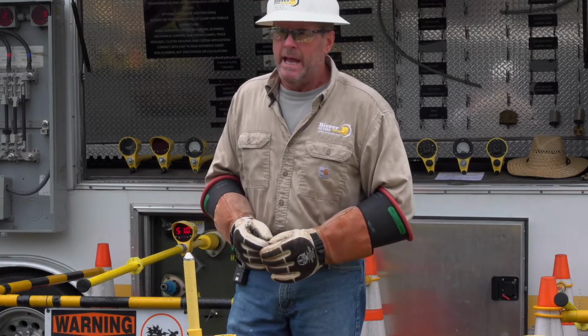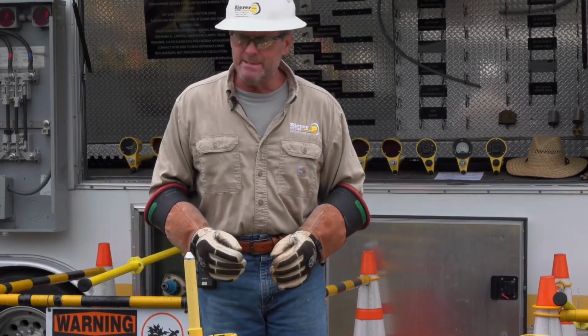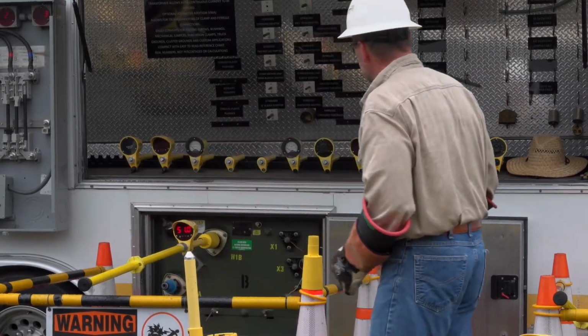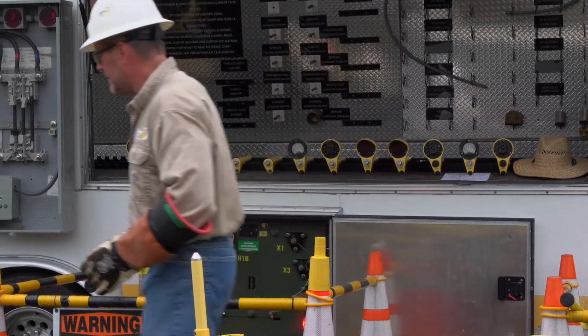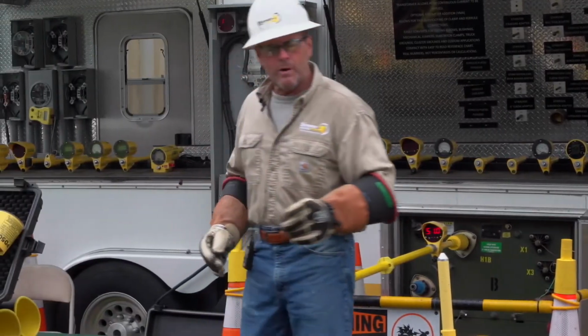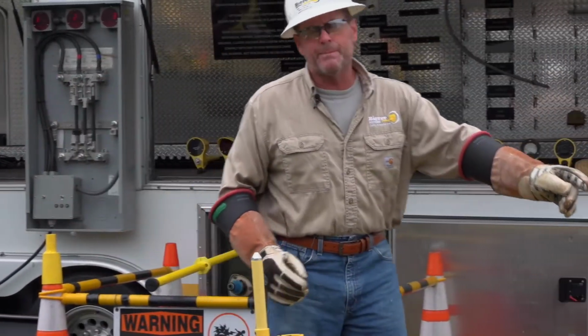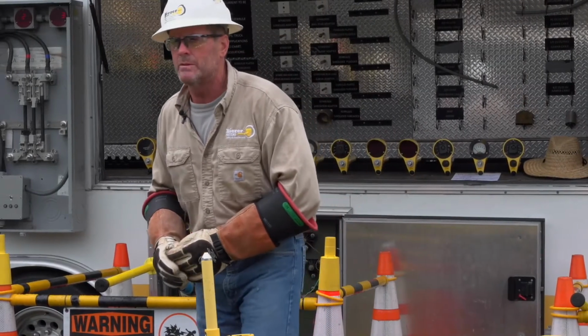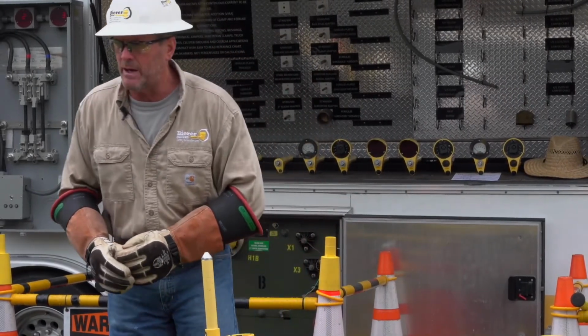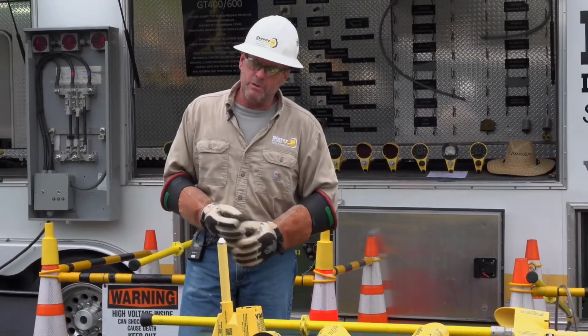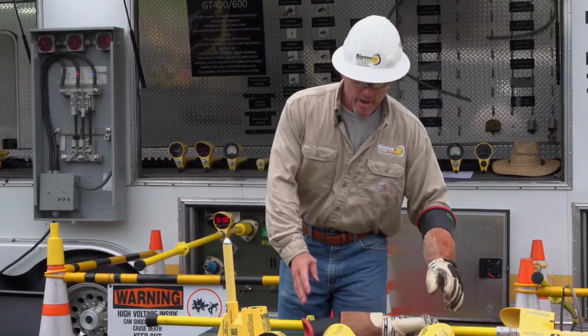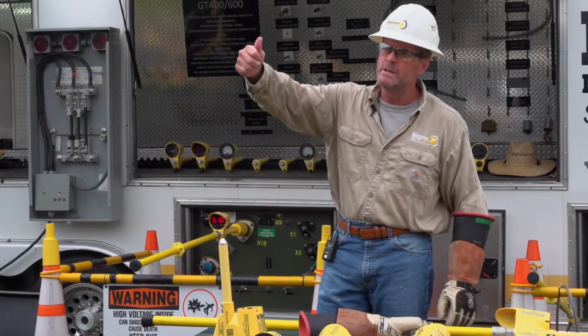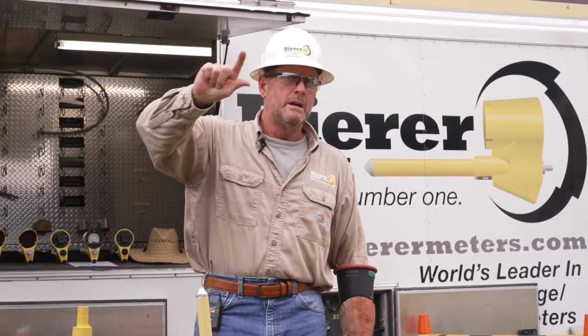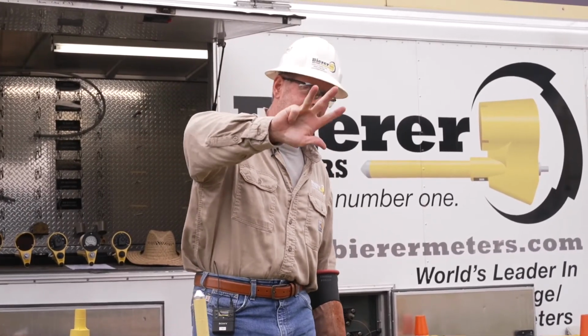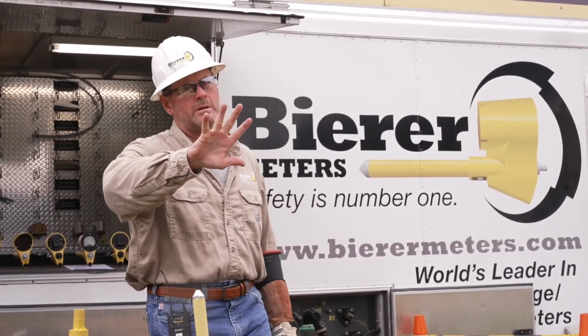When you're using these meters, it's important to always use direct contact. So what we're going to do is — you're typically trained open, test, ground. How we like to train is we're going to add a couple steps: test, open, test, test the tester, ground.